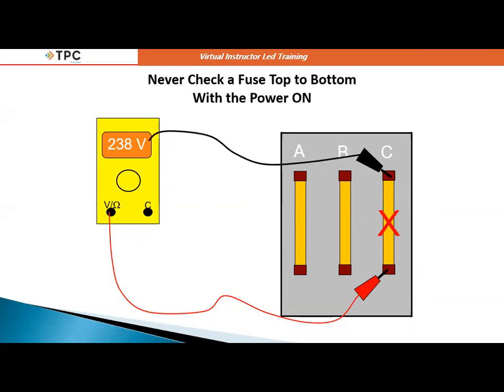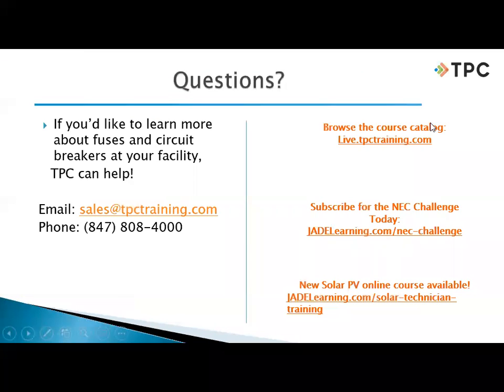Because notice, we were reading 480 volts before. All of a sudden, I went to 238. And so now my fuse is in series with the windings of that motor. And so if I do this, I could energize something on the load side of this, or I'm going to get some false readings. And so they do not want us to go from the top to the bottom while we are energized. That is just going to be a no-no.